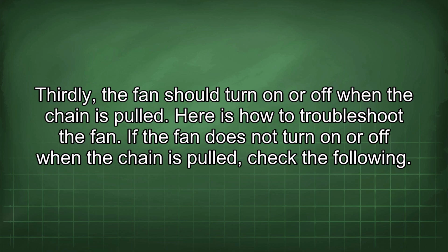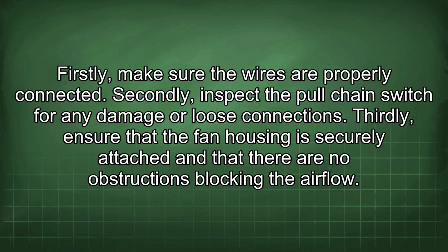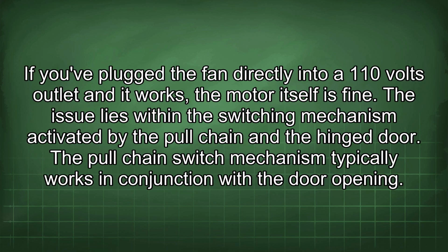If the fan does not turn on or off when the chain is pulled, check the following. Firstly, make sure the wires are properly connected. Secondly, inspect the pull chain switch for any damage or loose connections. Thirdly, ensure that the fan housing is securely attached and that there are no obstructions blocking the airflow. If you've plugged the fan directly into a 110 volts outlet and it works, the motor itself is fine. The issue lies within the switching mechanism activated by the pull chain and the hinge door.